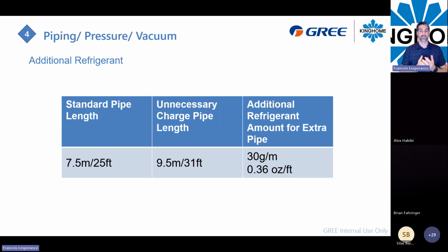Standard length pipe, it's 25 feet away from the indoor and the outdoor unit. The minimum is 10 feet. Okay, so always use a 10 feet minimum as a reference. And if you have, you can fit to 31 feet without adding refrigerant. Because we have those accumulator and liquid receiver, you don't have to remove refrigerant if you have a 10 feet piping length. Okay, so you don't have to, at any point, remove refrigerant on the system. But there's enough refrigerant to feed the systems without adding it till you reach that 31 feet long piping. If you have more than 31 feet, then you will have to add more refrigerant.